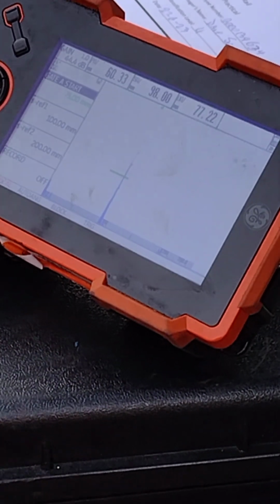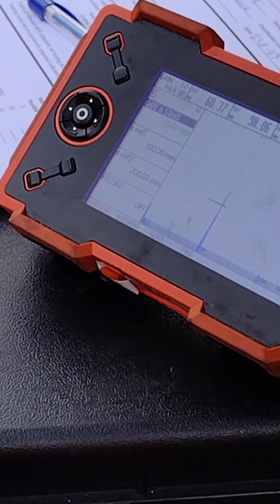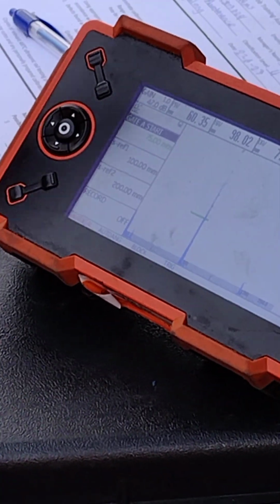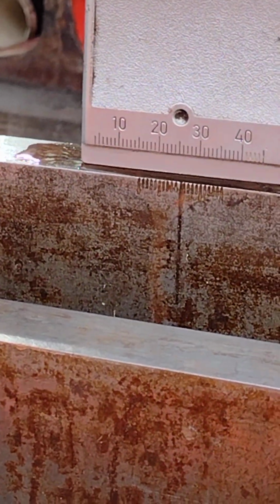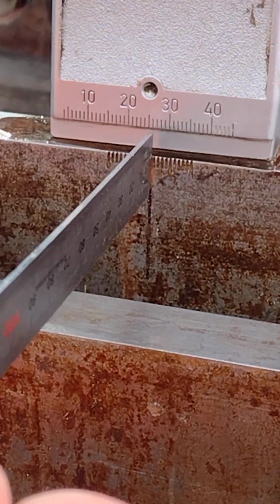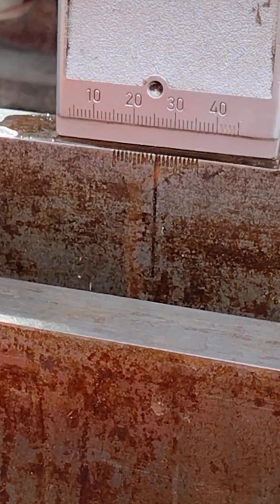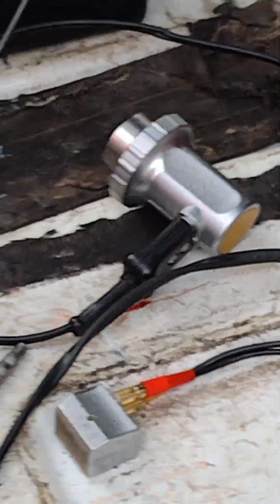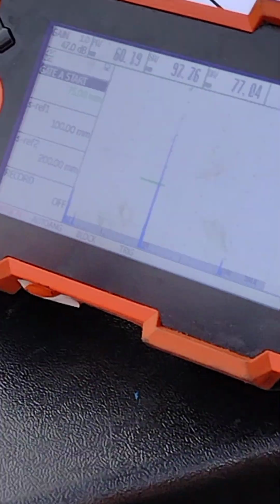we'll then auto 80 that, and then we'll check our index point. Our index point lines up with that slot, and it's pretty much 25 millimeters, maybe 25 and a half. We'll then go down to record our first reference.